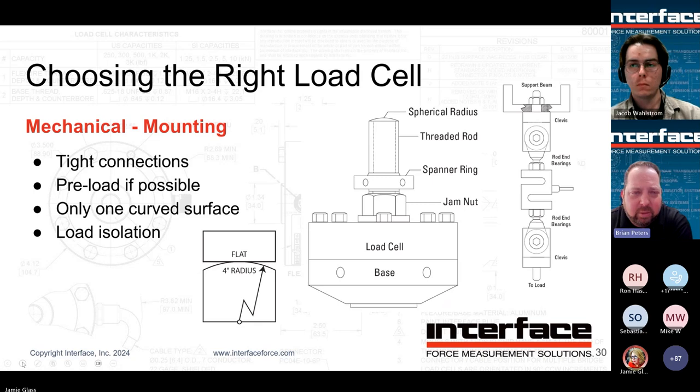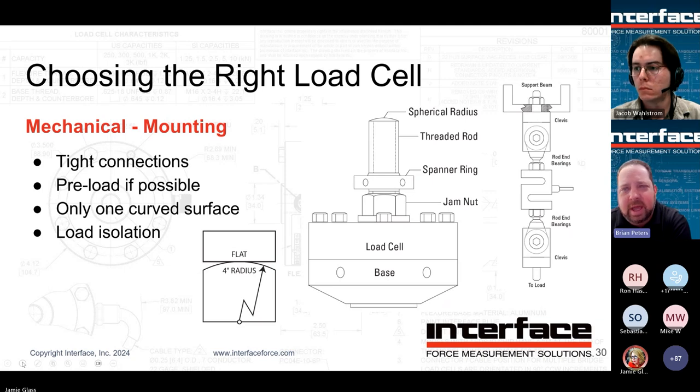So you'd want to have a flat surface interacting with that as depicted on the picture on the left. Our cal grade sensors come with pre-installed cal adapters, which oftentimes customers don't notice, but the tops are actually spherical. So you have the choice of loading through the threads or directly on the end of that if it's compression only if you want to. But basic test setup is well depicted on the right with essentially some rod end bearings to decouple the sensor from any potential side or bending loads. May not be able to do that, but that would be the preferred setup, of course. And that way you ensure that the only loads going through the sensor and through the bridge are going to be axial in nature.